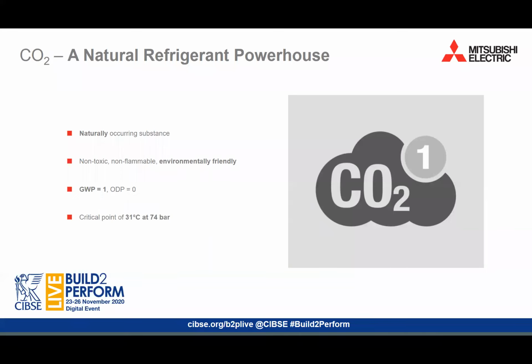The use of CO2 refrigeration in sea transport enabled the growth of the world fresh food market, and it reigned until the middle of the 1940s, when newly invented synthetic refrigerants became popular owing to their higher efficiencies and lower operating pressures. However, over the last 40 years, the environmental consequences of CFCs, HCFCs, and the realization of the global warming potential of HFCs have turned the focus back to naturally occurring refrigerants and HFOs.